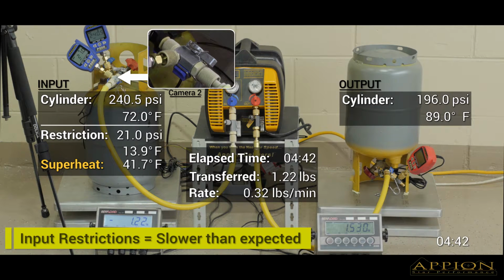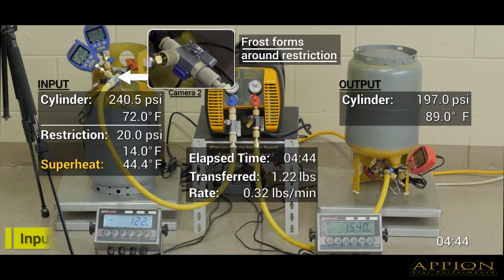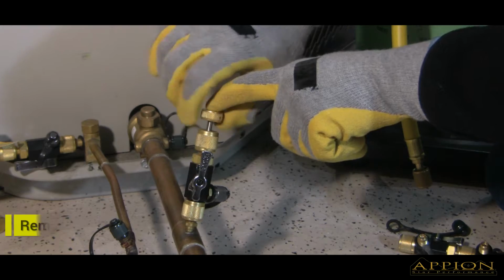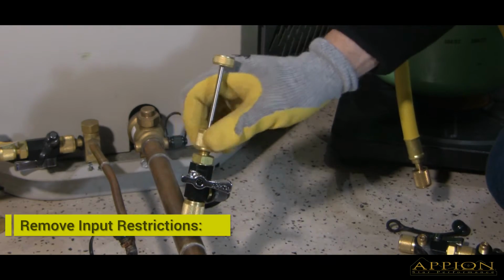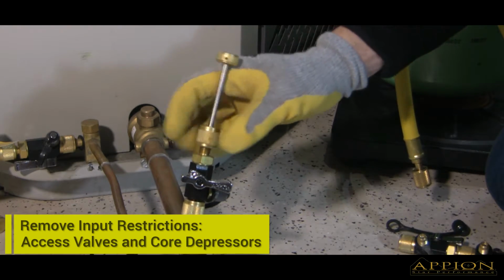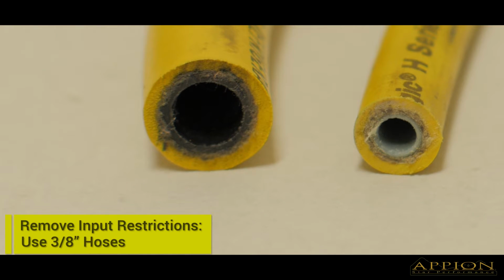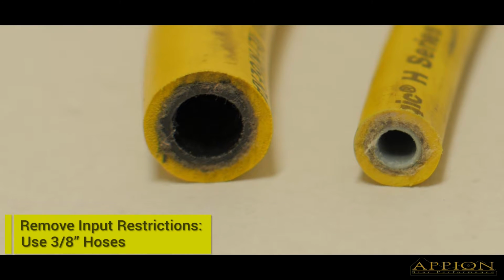Another sign of input restrictions is condensation or frost. This may be at the hose fittings, access valve, or near tight bends in the condenser tubing on the system. Don't get heated up by input restrictions. Remove Schrader valves and core depressors and use 3/8 hoses to allow full liquid flow to reach the recovery machine.